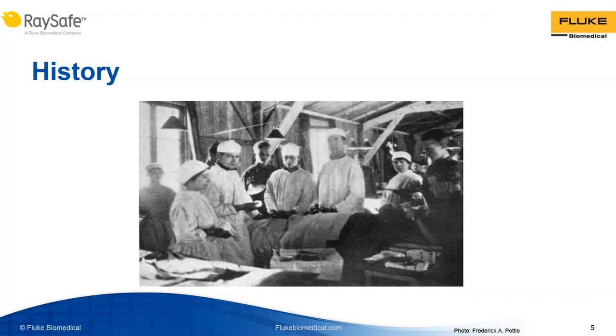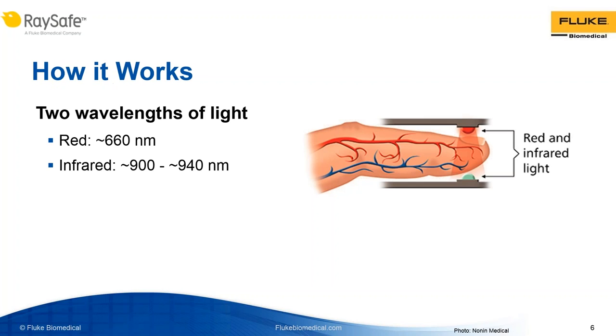Here's how it works. Pulse oximeters shine light through the human body — typically a finger, but also feet, earlobes, and foreheads are used. Some oximeters reflect light off the body part rather than shine light through it. In the most common configuration, the oximeter shines two different wavelengths of light through the patient's finger using LEDs, one at a time. The two wavelengths are red, approximately 660 nanometers, and infrared, approximately 900 to 940 nanometers. These wavelengths are approximate because every manufacturer might be a little different. Red is the slowest frequency of light in the visible spectrum, and infrared is an even slower frequency just outside the visible spectrum.